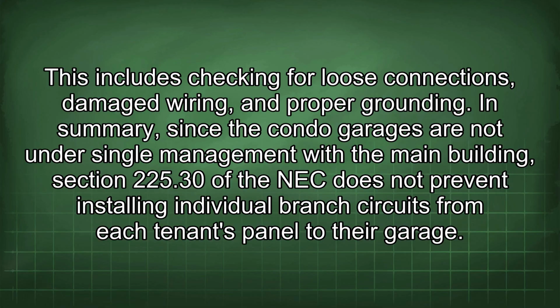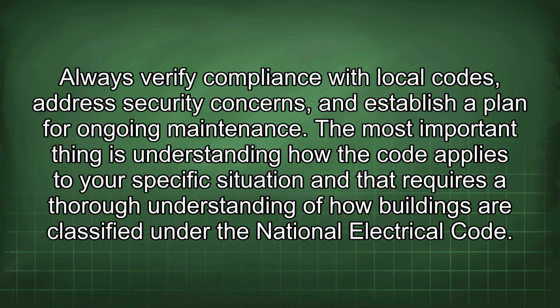In summary, since the condo garages are not under single management with the main building, Section 225.30 of the NEC does not prevent installing individual branch circuits from each tenant's panel to a garage. Always verify compliance with local codes, address security concerns, and establish a plan for ongoing maintenance. The most important thing is understanding how the code applies to your specific situation, and that requires a thorough understanding of how buildings are classified under the National Electrical Code.